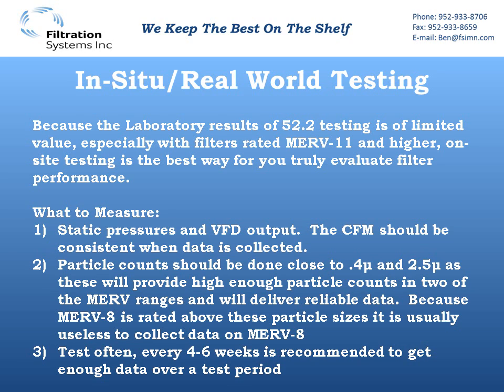If the CFM drops, your static pressure usually drops and your VFD is usually down as a result of the lower CFM. At the same time, if the CFM is higher when you go to collect data than what it was the previous time, it's going to skew the results. So you need to either make a note of that or somehow override your controls to make everything consistent when you take the information.